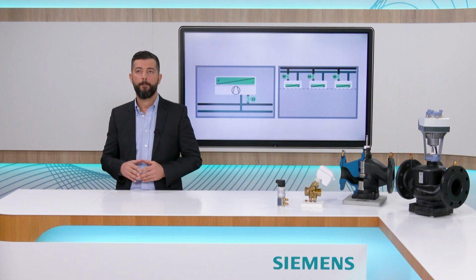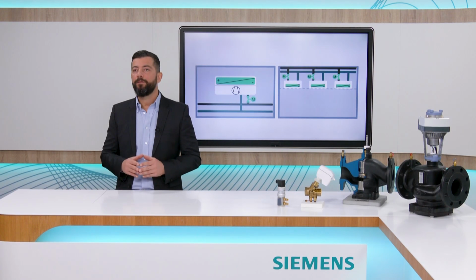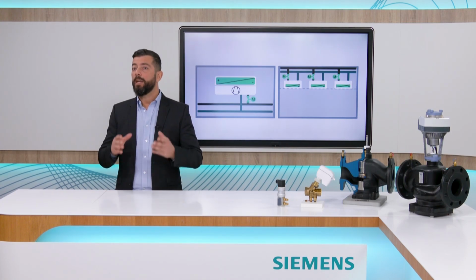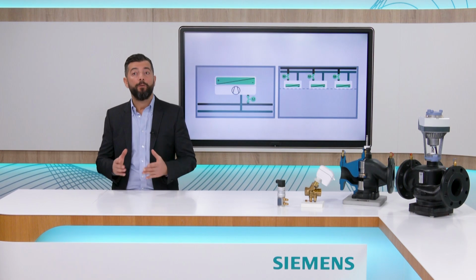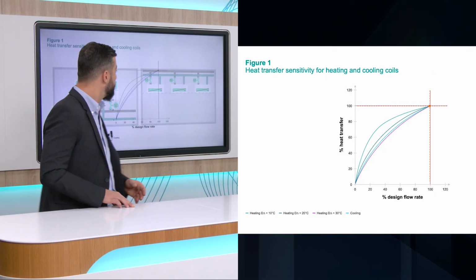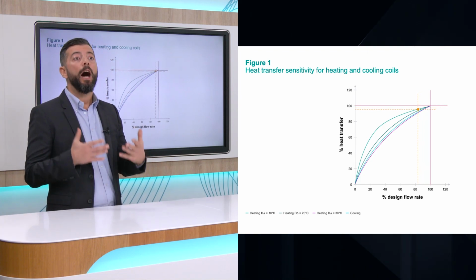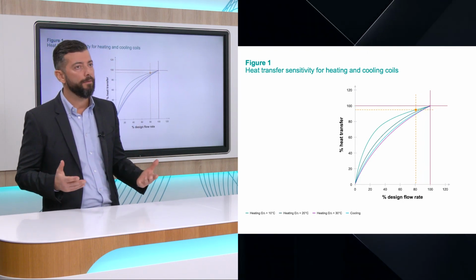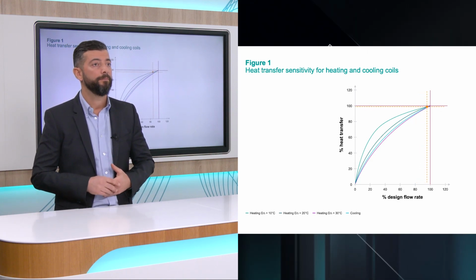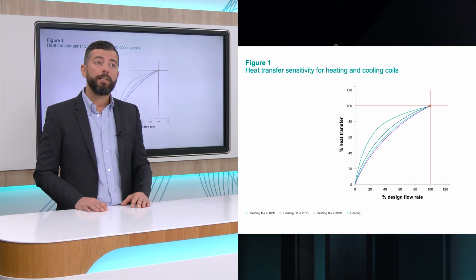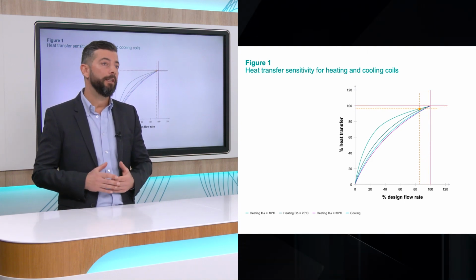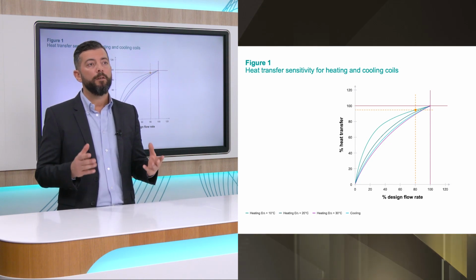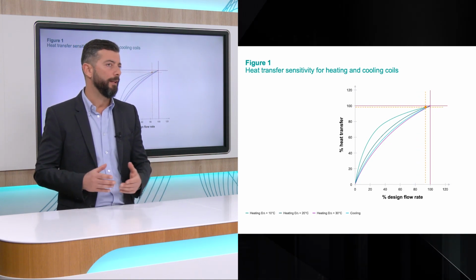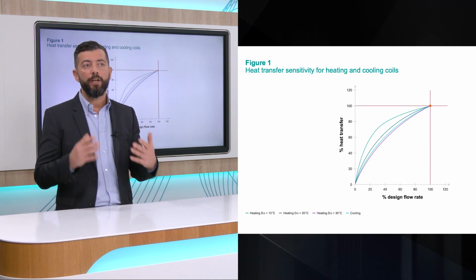under control. Instead, if you consider active units where the air is forced across a heat exchanger, there is more sensitivity to actual flow rates, especially if the temperature differential between supply and return is high. In this chart, you can see how active heating or cooling coils behave and better understand what that means. The good news is that whenever the delta T is limited to a maximum 10 degrees, then a deviation in the flow of up to plus or minus 10% generates a very limited change in the heat transfer.